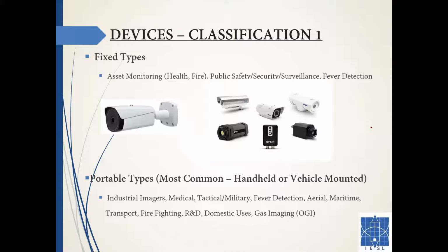And lastly, gas imaging, what we call OGI, optical gas imaging, is a very popular and rapidly rising technology where you can see leaking gases using these cameras. The latest camera model from a reputed supplier has options to see anomalies such as electrical and mechanical issues, and it has a separate dedicated mode to see leaking sulfur hexafluoride gas, SF6. So that's the thing now.